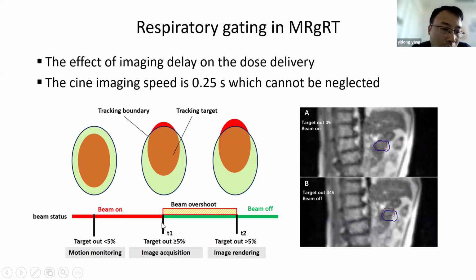So you see, when the target is inside the boundary, the beam is on. But when the target moves out of the boundary, we want to immediately stop the beam. But we acquire the positioning information or the volume information from these dynamic MRI images. That means we only know this position after we get the image. So the imaging time is about 0.3 seconds. That means the latency is at least more than 0.25 seconds.